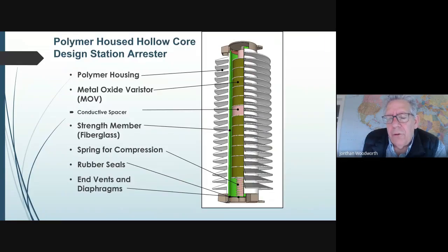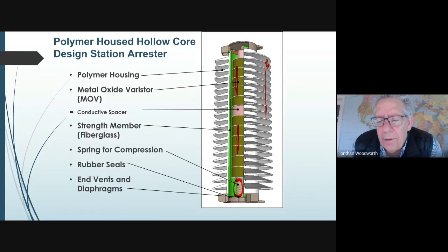Inside the arrestor, as I was showing you earlier, this is a rubber housing. This is a station class arrestor. There's a rubber housing on the outside. Quite often you'll see this made out of porcelain still. But on the inside, we have these metal oxide varistors, same as we saw in that little presentation on the distribution arrestor at the start. There's usually a spring to keep things under pressure, and there's a top terminal and bottom terminal to make sure that it can stand by itself, or it can support a line, or if it does fail, it doesn't blow apart. So this is what a polymer housed station class arrestor looks like.